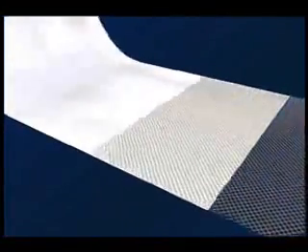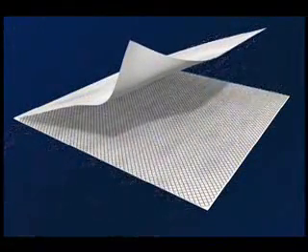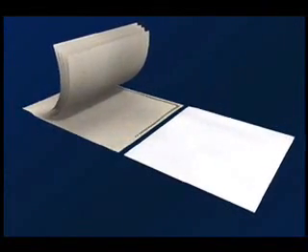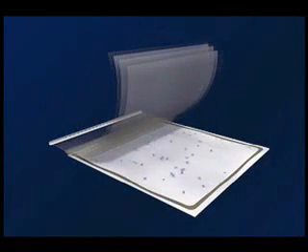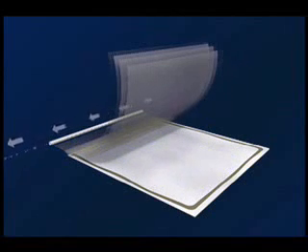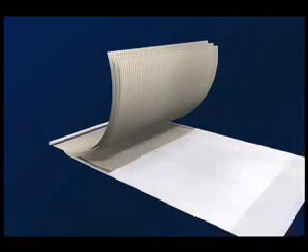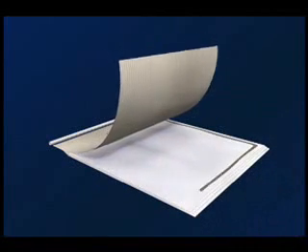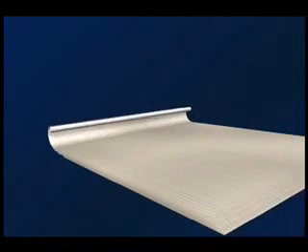The membrane flat sheet is then combined with a sheet of feed channel spacer. This provides turbulence and creates space between the membrane sheets to allow uniform flow of the water to the entire membrane surface. The leaves of membrane and feed channel spacer are then combined with a sheet of permeate spacer which provides open flow channels for the permeate even under high pressure. The leaves are glued along each of the three exposed sides and then rolled around the core tube.